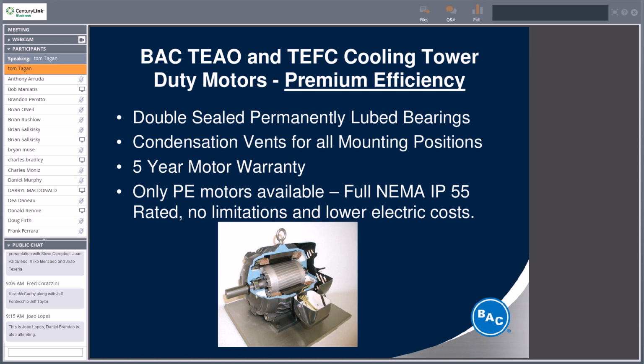The motors. BAC uses TEAO and TEFC motors. Premium efficiency, double sealed, permanently lubricated, with condensation vents for cooling tower service. I mentioned the 5-year motor warranty, which is again held through the motor manufacturer. And as with most equipment these days, only premium efficient motors are available. So on any new installation, you're going to get a premium efficient motor, inverter duty ready for VFD service, and it's going to be reversible.